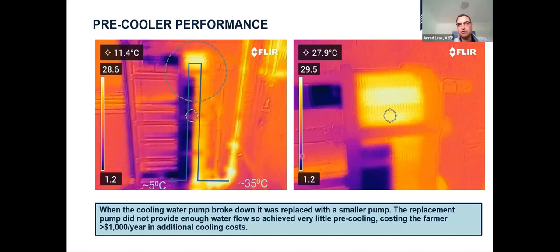You could actually see when you zoom in on the top half of the heat exchanger - the milk goes through the pre-cooling section, works its way up, across the top, then down into every second channel on the chiller section. We saw the temperature wasn't going down much at all. After asking a few more questions, we got to the bottom of it quickly: a few years earlier, the pump recirculating water through the pre-cooler had broken down and was replaced with a smaller pump that wasn't getting the flow rate needed. So there was an opportunity - changing back to a proper size pump would get around 10 degrees extra cooling with the right flow rate.